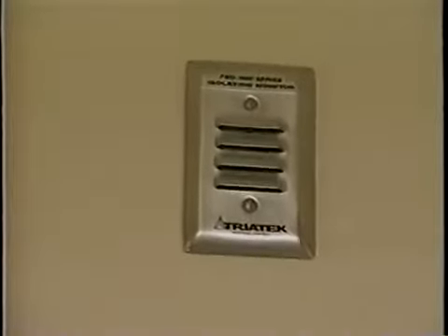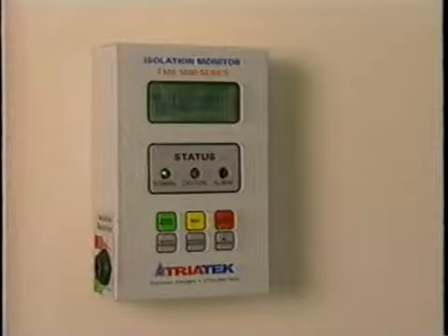A room pressure monitor is an electronic device that continually measures the pressure across a room boundary. It consists mainly of a sensor installed through the wall and a panel that displays the sensor pressure reading, usually in units of inches of water gauge. The measured pressure is compared to a reference pressure value. The monitor is usually programmed to sound an alarm when the pressure falls below the reference pressure and stays there for a certain length of time.